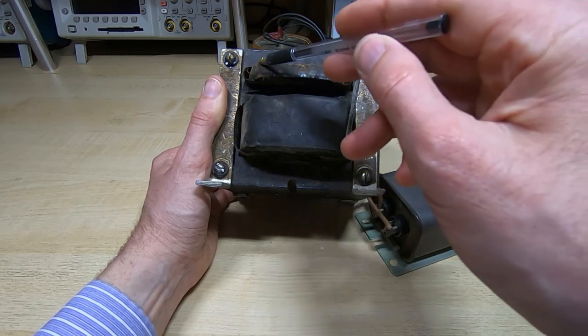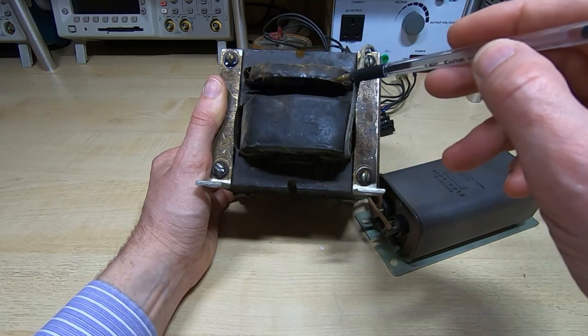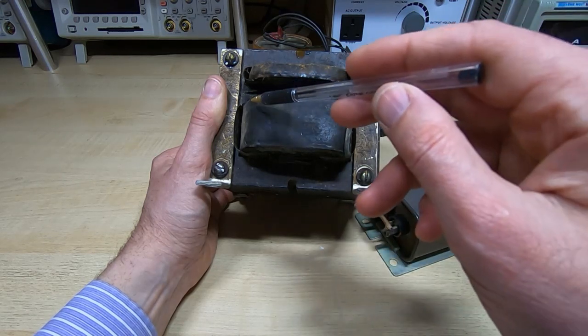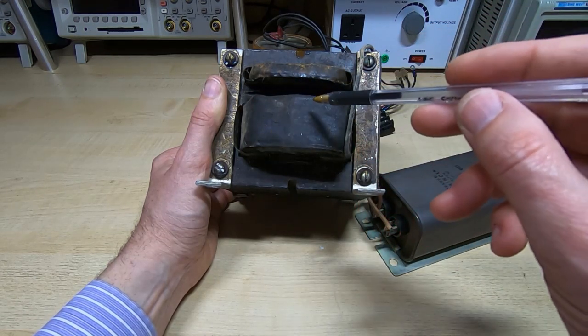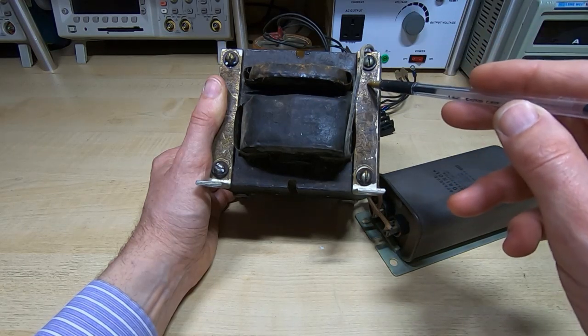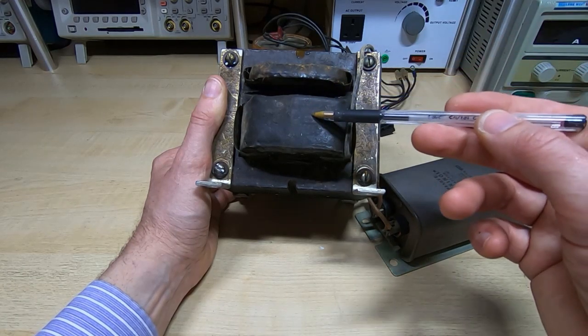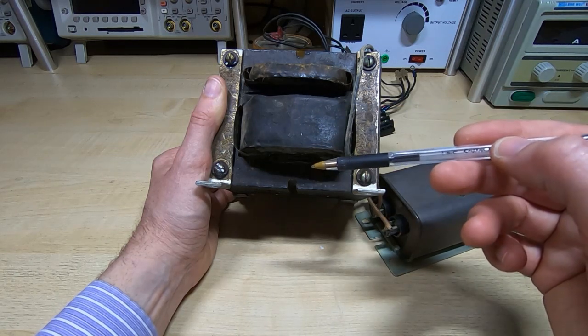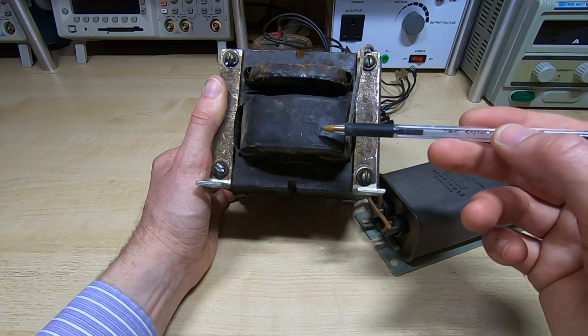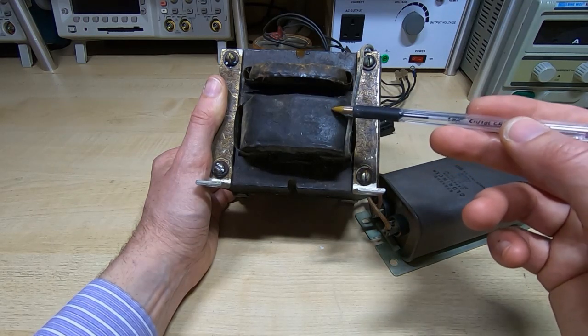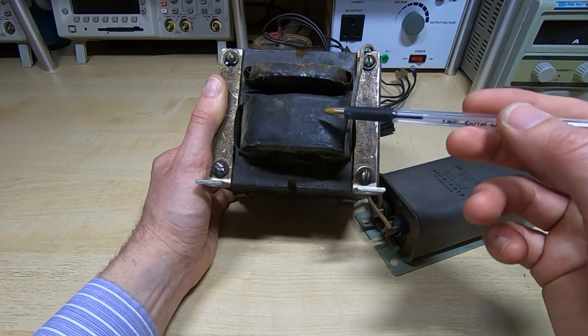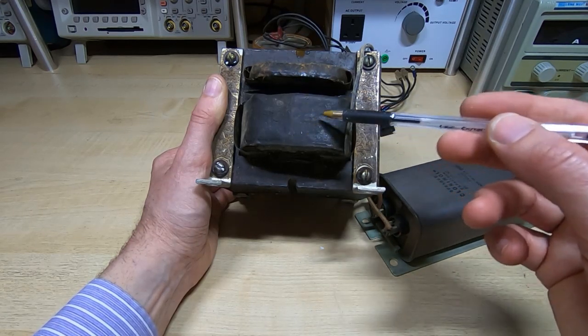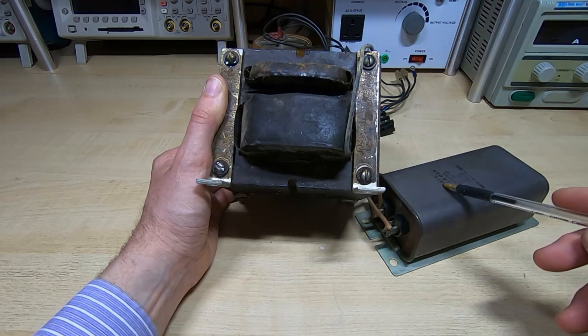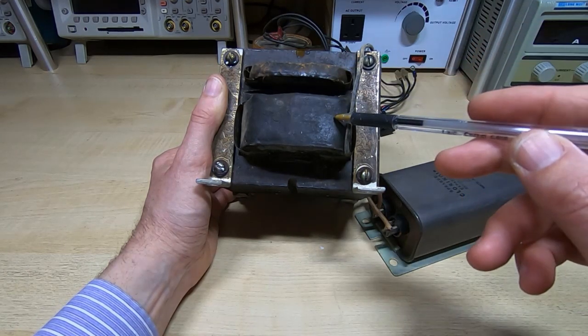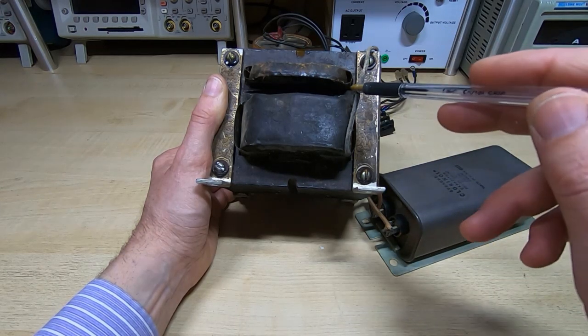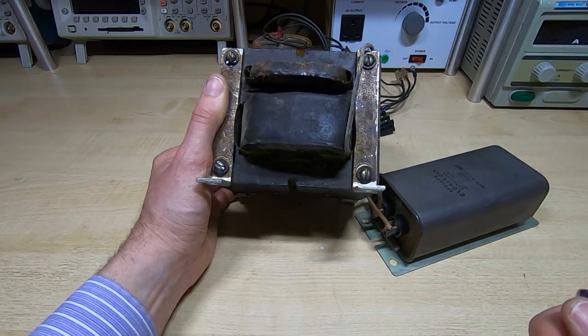So in this particular transformer, this top section is actually the primary winding. So that's what we apply the mains input to. And at the bottom we have the secondary windings. And the secondary windings on this particular transformer are in three parts. We have the basic output part of the transformer, that's our main secondary voltage output. That's the one that we were deriving the voltage from that we looked at in the previous video. There's then another winding in this section that is only connected to this resonant capacitor. And then in this particular transformer there's a third winding for other purposes, but that's not necessary and it's not part of the ferroresonance system.